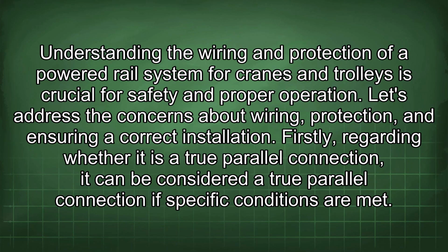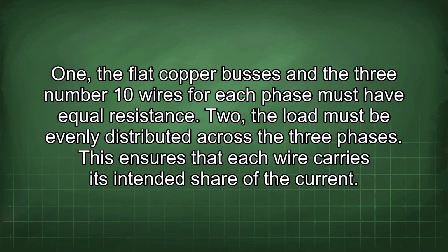Understanding the wiring and protection of a powered rail system for cranes and trolleys is crucial for safety and proper operation. Let's address the concerns about wiring, protection, and ensuring a correct installation. Firstly, regarding whether it is a true parallel connection, it can be considered a true parallel connection if specific conditions are met. 1. The flat copper buses and the 3 number 10 wires for each phase must have equal resistance.